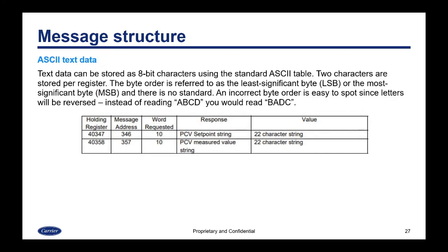Text data can also be stored as 8-bit characters using the standard ASCII table. Two characters are stored per register. The byte order is referred to as the least significant byte or the most significant byte, and there is also no standard to this. An incorrect byte order is easy to spot since letters will be reversed — so instead of a message saying ABCD it would read BADC, since each word of two bytes will be reversed.